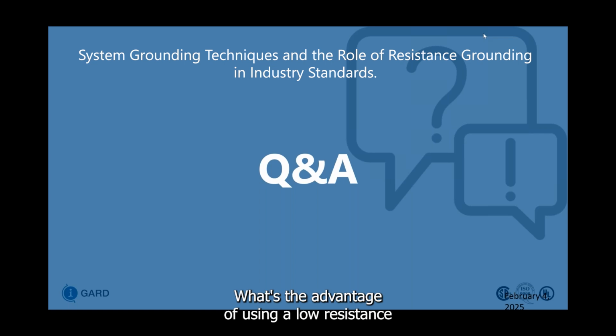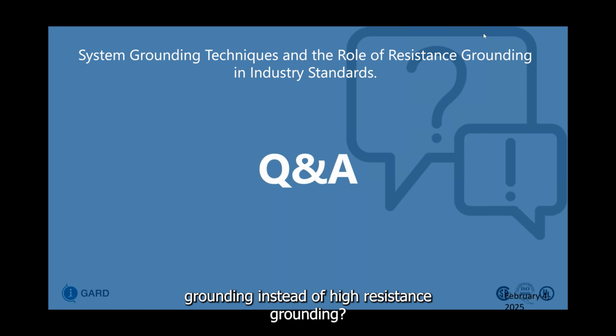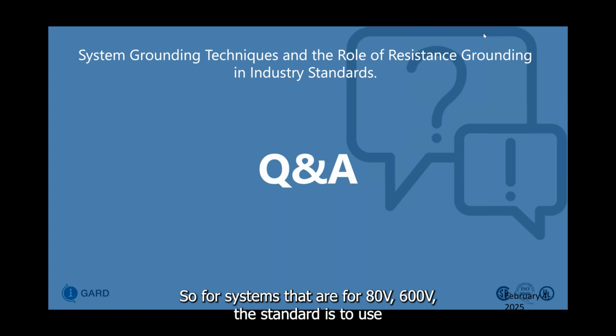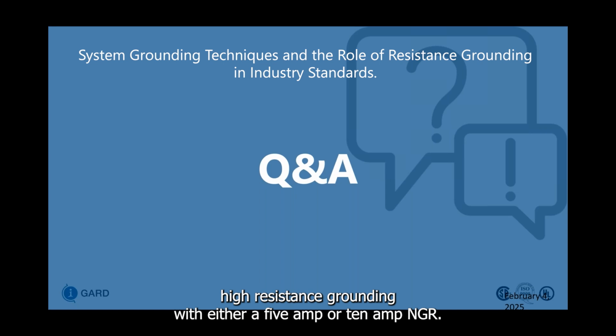What's the advantage of using low resistance grounding instead of high resistance grounding? In which scenario do I use it? So for systems that are 480 volts, 600 volts, the standard is to use high resistance grounding with either a 5 amp or 10 amp NGR.